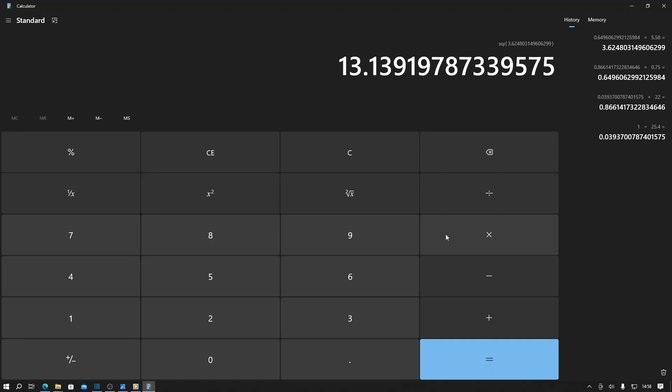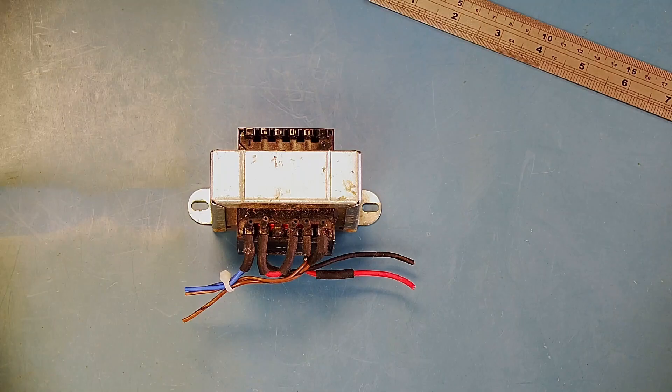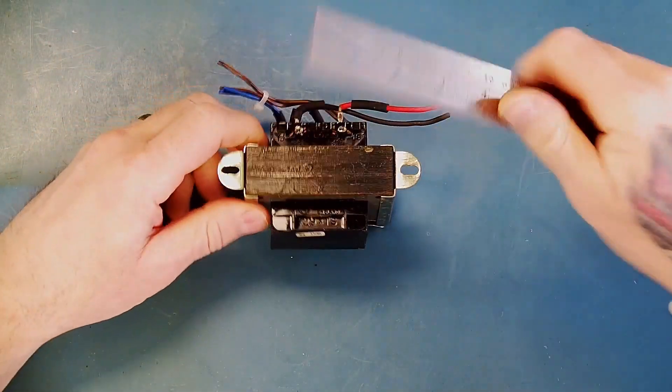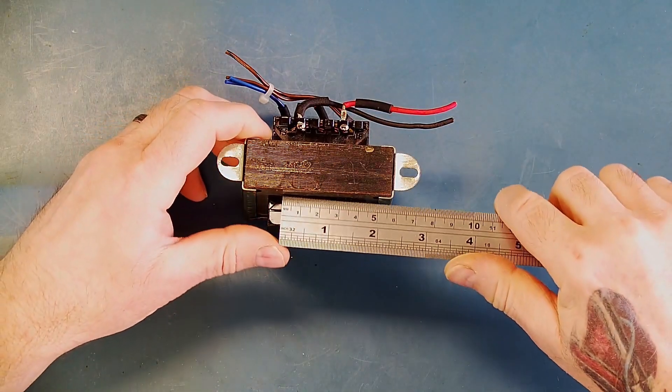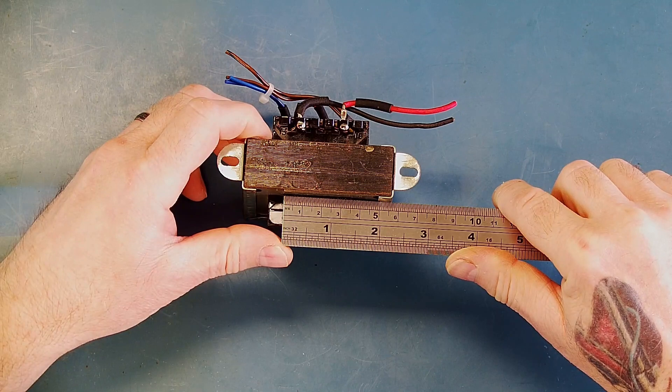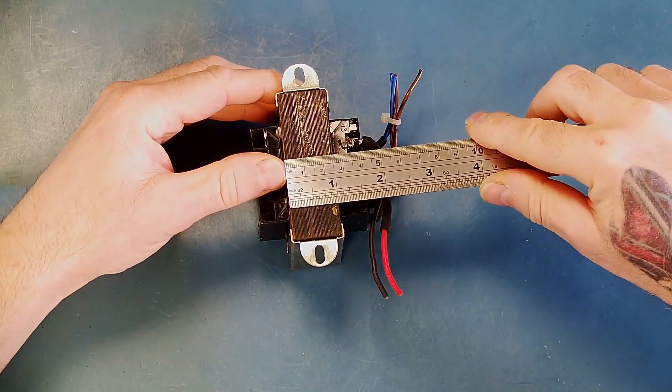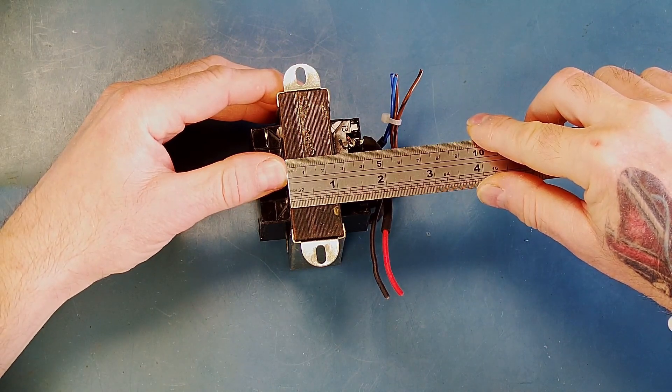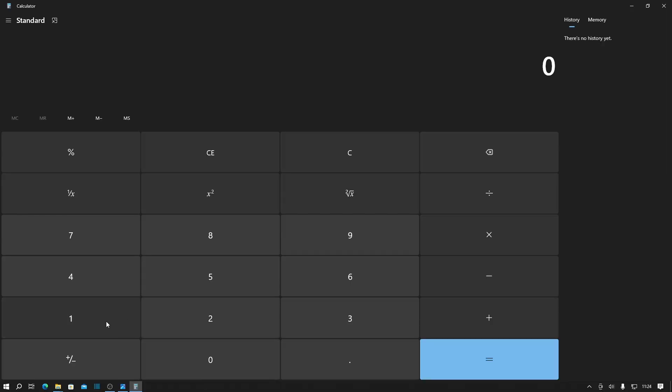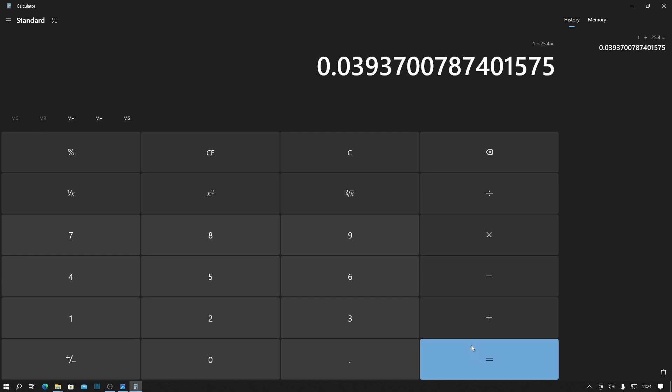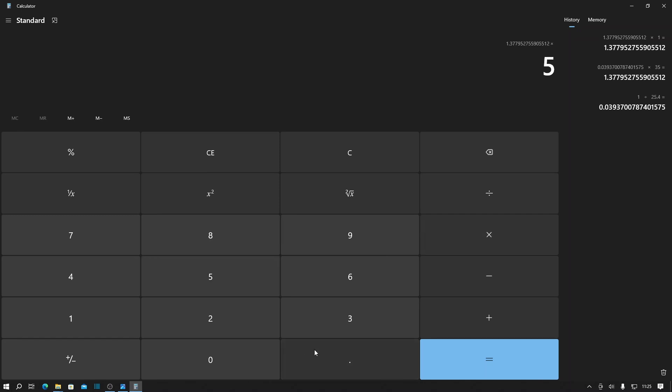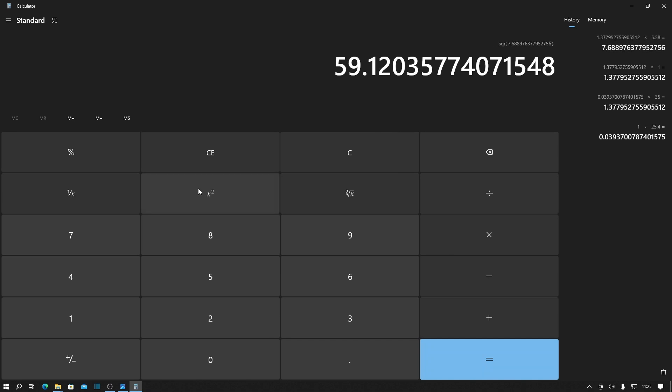Let's go ahead and do one that has an unknown VA rating, which is approximately 35 millimeters by 25 millimeters. That's our constant so multiply that by the 35 millimeters. I think just for simplicity we'll just multiply that by one because it's basically a one inch stack. Then we multiply that by the constant factor and then square that, and that gives us a VA rating of 59.1. I believe this is a 60 VA transformer officially, so that works out quite well.